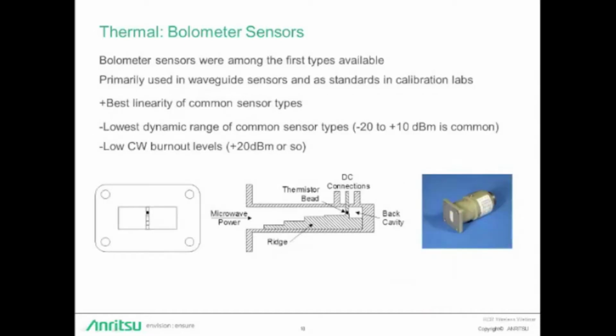Bolometer sensors were among the first type of RF microwave power sensors available. Today, they're primarily used in waveguide sensors and as standards in calibration labs. These sensors generally have the best linearity of the common sensor types. However, they tend to have the lowest dynamic range of common sensor types, somewhere from -20 to +10 dBm is typical. Bolometer sensors also tend to have low CW burnout or damage levels, around +20 dBm or so. At Anritsu, we currently use thermistor sensors as our working standards for calibrating our sensors.